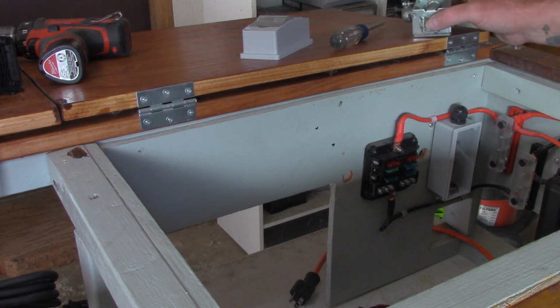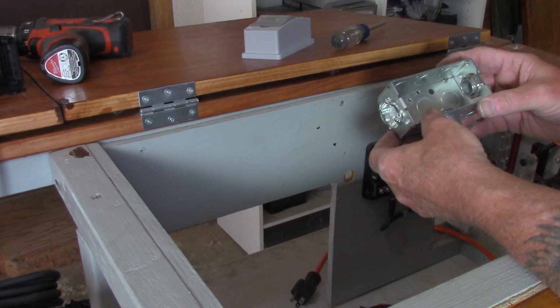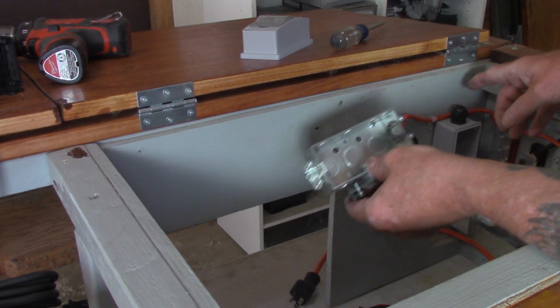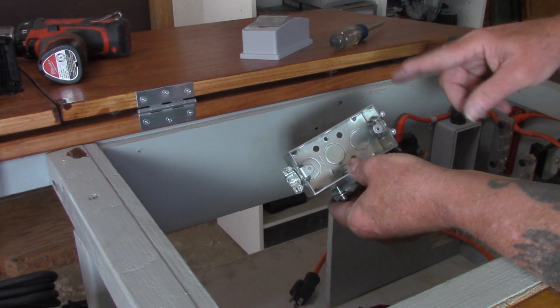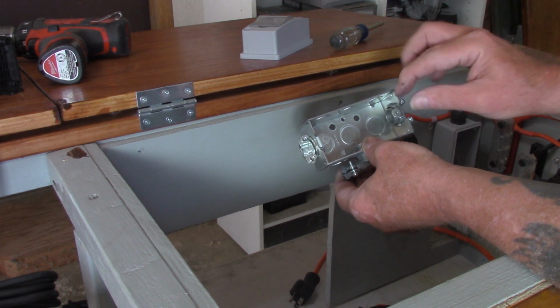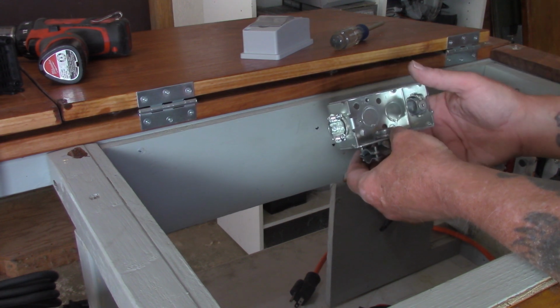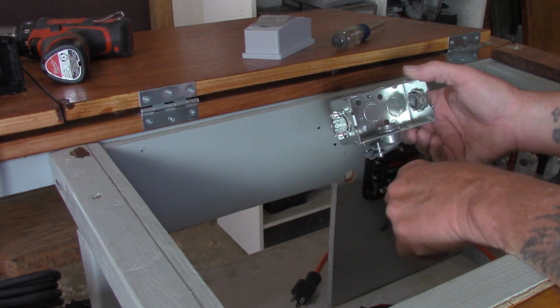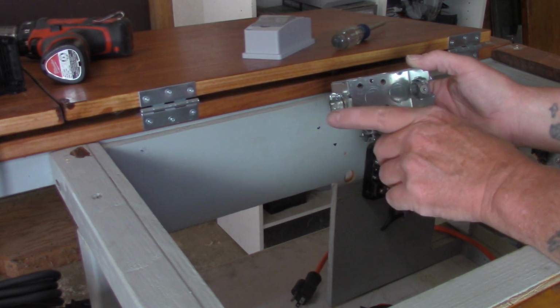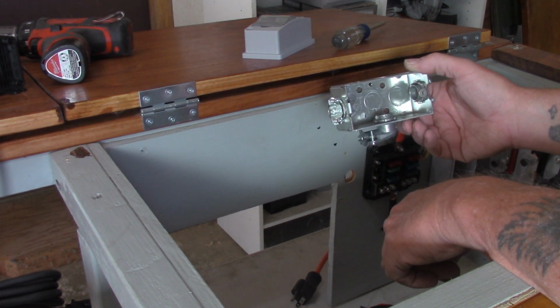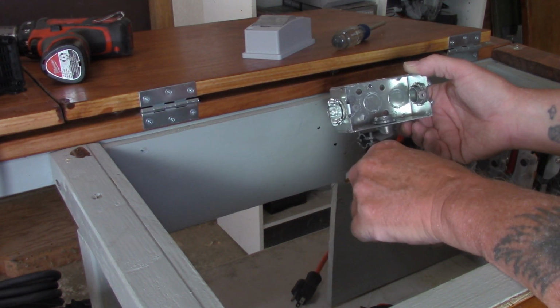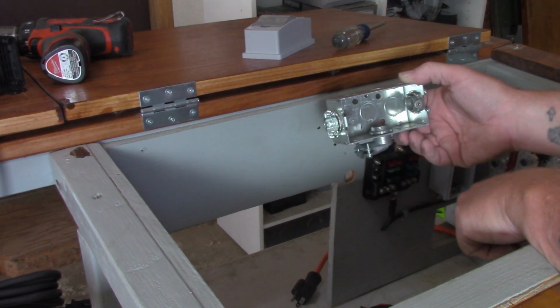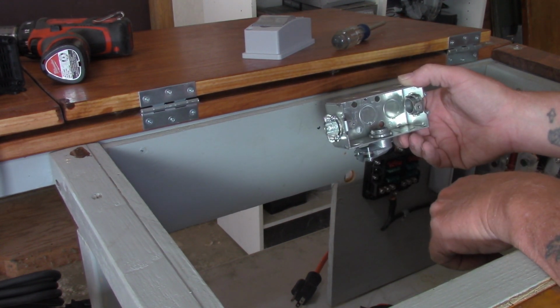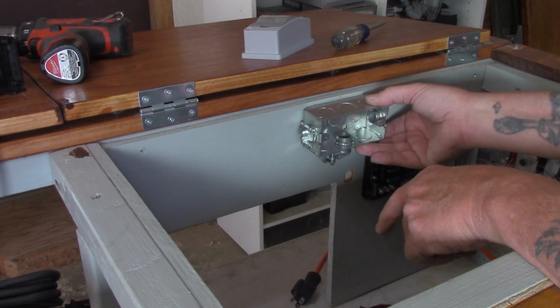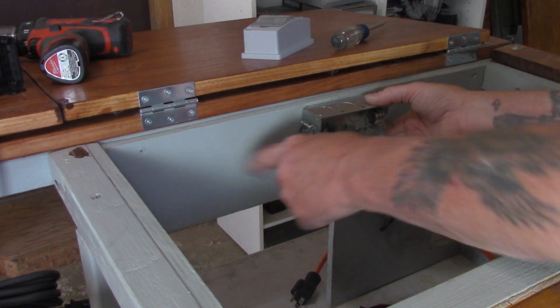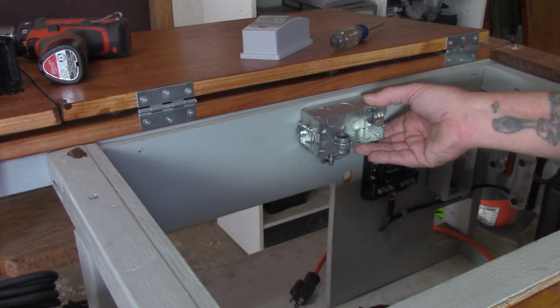The next thing we install is going to be this three-way junction box. It comes from the circuit breaker over to this input, and here it'll split into two. One of them will go to the battery charger, and this other one will go over to the three-way switch, the voltage sensing switch, to provide shore power to that inlet. And then the next thing we put up after this goes up will be the three-way switch right over here. Okay, let's get busy on that.